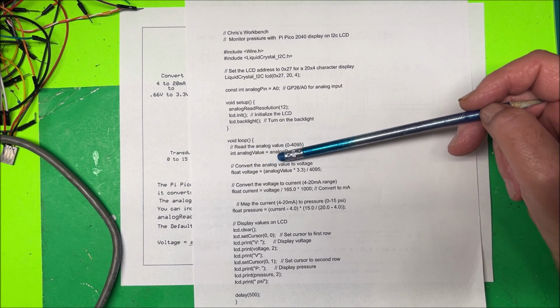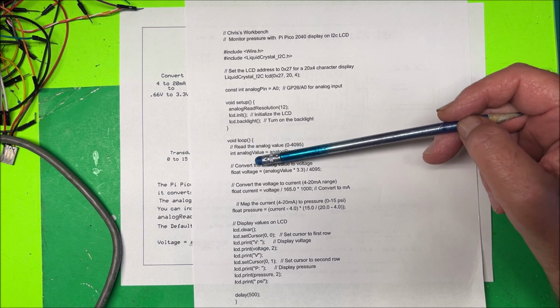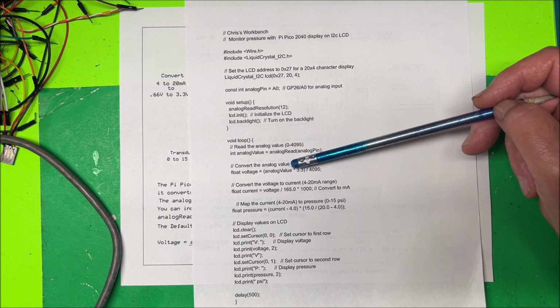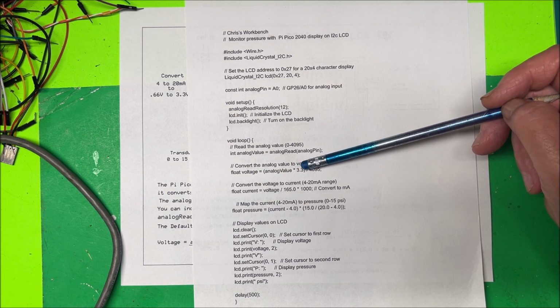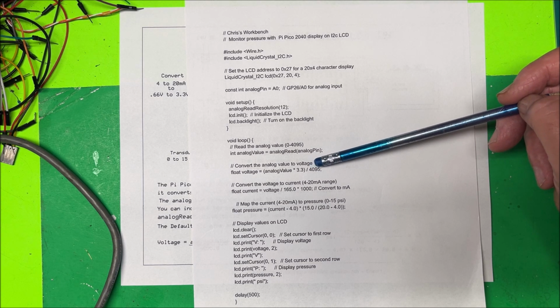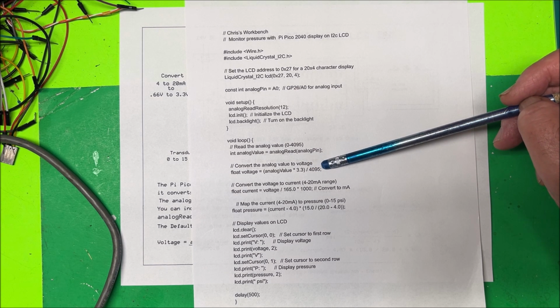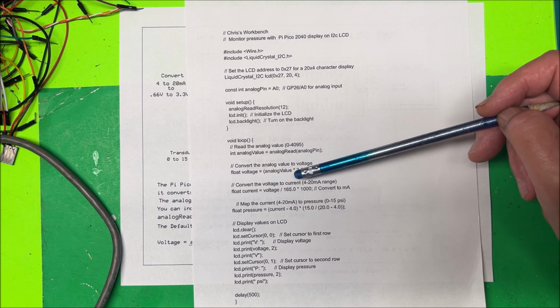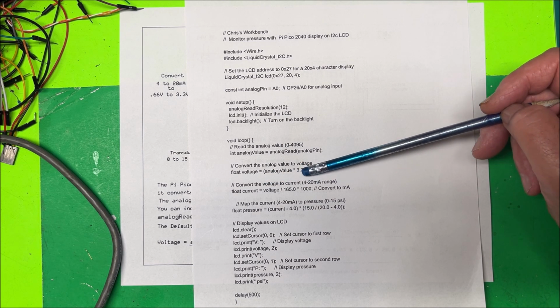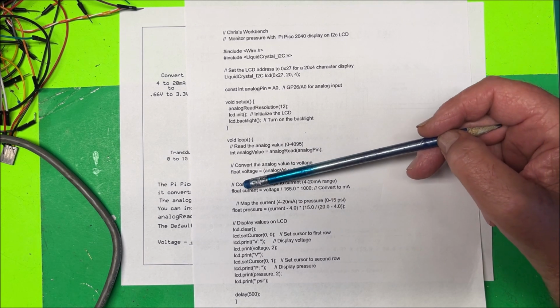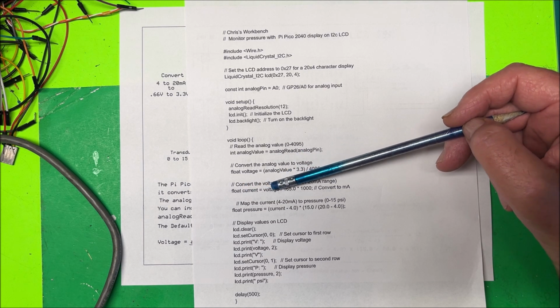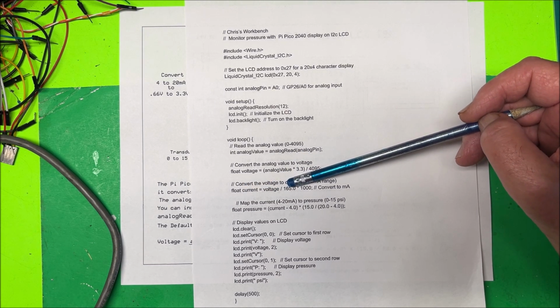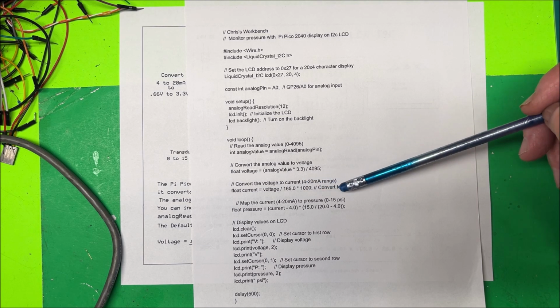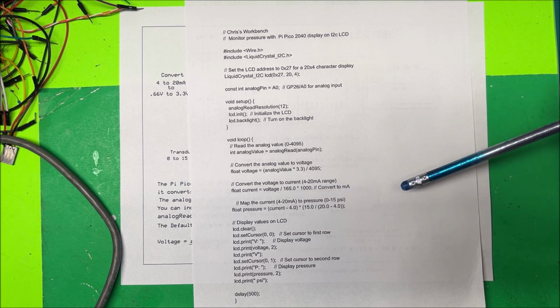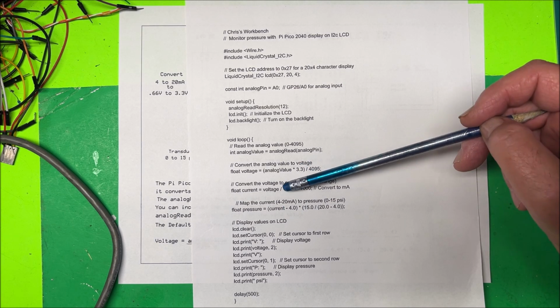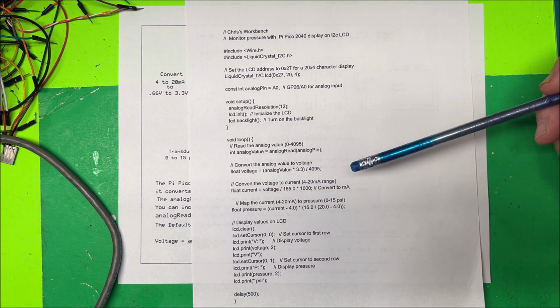And then we convert the analog value to voltage. So float voltage is equal to the analog value times your 3.3 divided by 4095. And then we're going to convert that voltage to current in the 4 to 20 milliamp range. So float current is equal to your voltage divided by your resistance times 1000 to get your milliamps. Now on the other sheet I had a different formula to convert voltage, but this one seems to be easier.